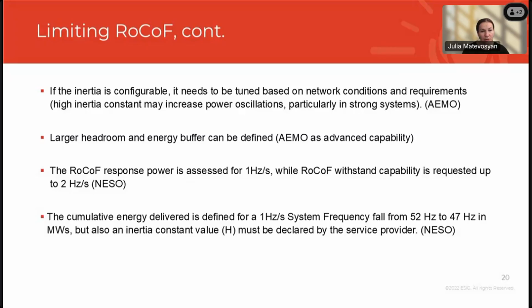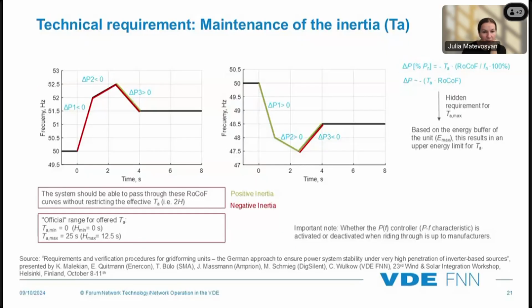National ESO tests response for RoCoF of 1 Hertz per second, and they also require withstand capability for RoCoF of 2 Hertz per second. And then there is also a test for cumulative energy during RoCoF as the frequency changes between 52 Hertz and 47 Hertz. This is again from VDE FNN. The resource under test is subjected to different rates of change of frequency. So this is like a frequency event with different rates of change of frequency over time.